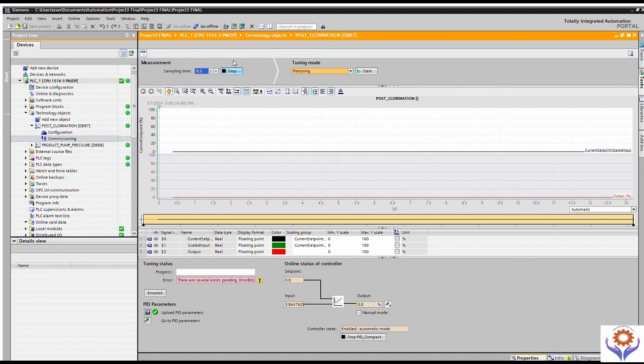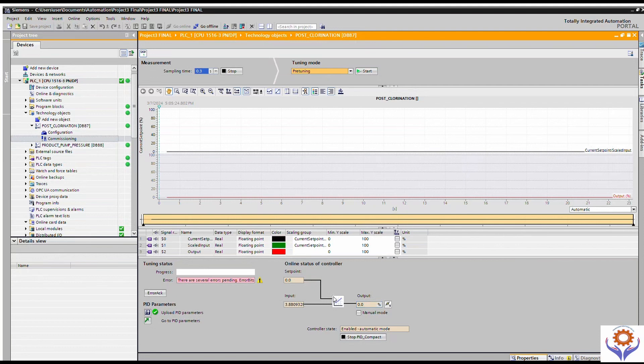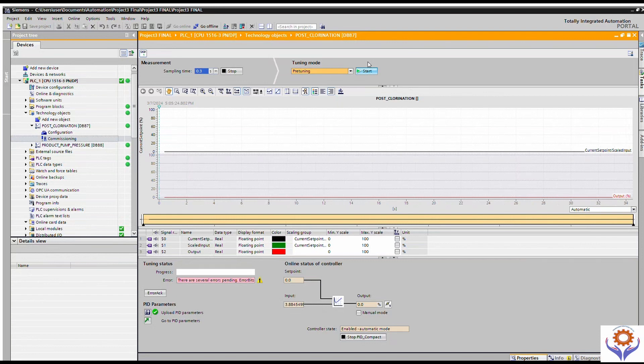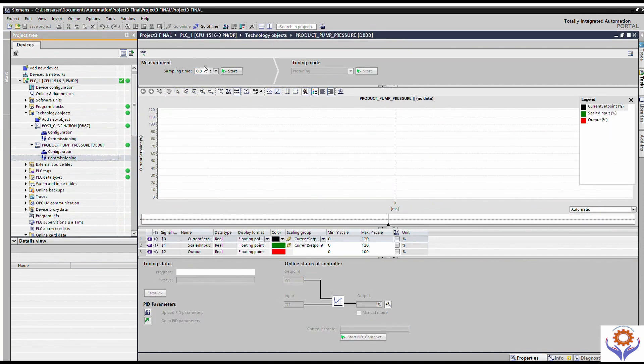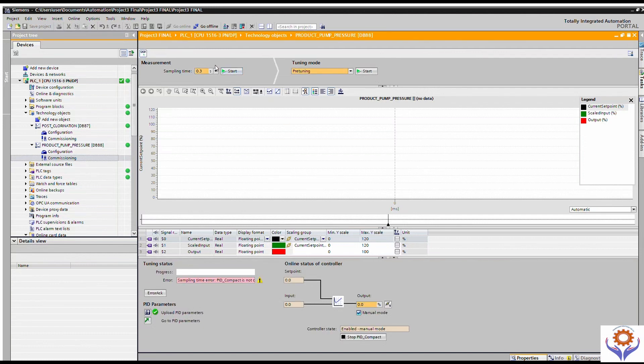In the Commissioning view, you can find the sampling values — it's 0.3 and I have started it, so you can see values appearing. If you need to do pre-tuning, select Pre-Tuning Mode and click Start — it will then start showing values. The input value is showing 3.87 and output is zero because the set point is not set in this project. If you set a set point, for example 3, it will tune based on that. For other product pump pressure, you can find the same things and see all the graphs.